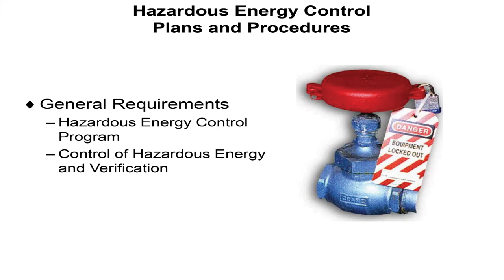Electrical hazards range from high voltage systems to low voltage systems. High voltage systems may include electrical substations with equipment, transformers, capacitors, and fuses, above ground and below ground power lines, and generators. Low voltage equipment may include pumps, miscellaneous machinery, hand tools, and electrical outlets. Only qualified persons with advanced training are permitted to work on energized electrical systems or equipment. Subcontractors are responsible for ensuring their personnel are properly trained and qualified on the electrical hazards present during work that is conducted on the SPR.